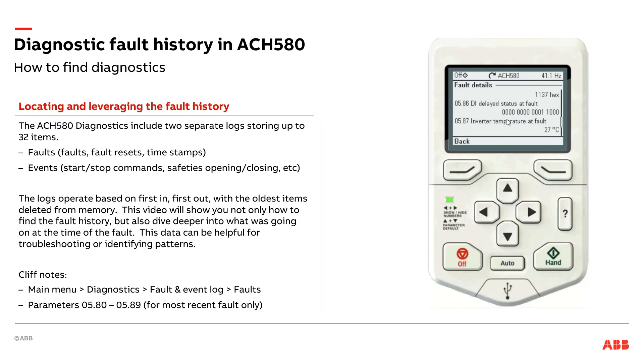Continuing down, I can see the inverter temperature at fault. The IGBTs were only at 27 degrees Celsius, which is quite cool — makes sense because I just have a little demo here. But in a traditional application, if it faulted because of a temperature or load related fault, that might have been 115 or 120 degrees Celsius, depending on the particular drive and frame size. In other areas we talk about inverter temperature in percentage, where 100% equals fault. But here we converted it directly to degrees Celsius to help field technicians understand what the temperature should be.